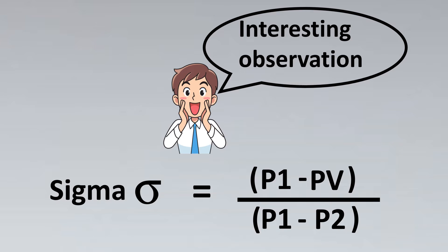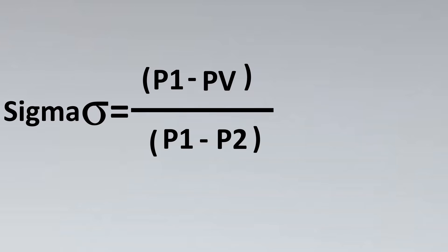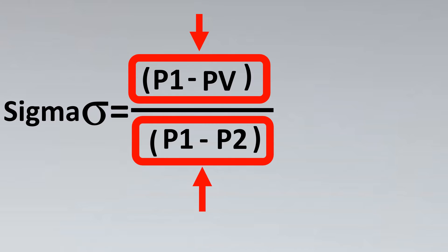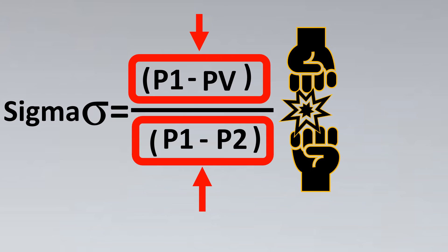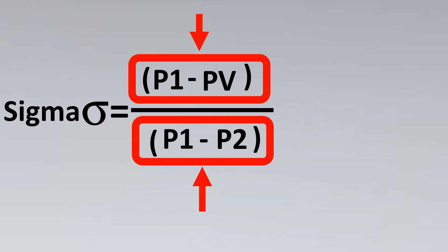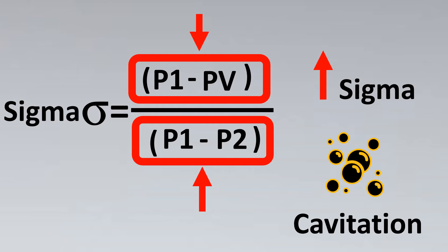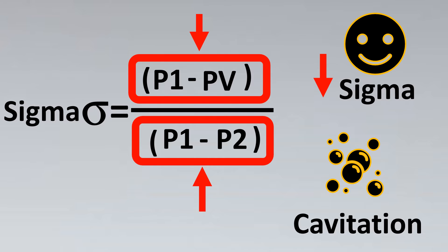But there is something more interesting to it - an interesting observation with respect to sigma value. The numerator and the denominator of sigma value are actually fighting with each other for cavitation. The higher the value of sigma (if the numerator wins), there's lesser chances of cavitation. If the value of sigma is less, there is very high chances of cavitation.